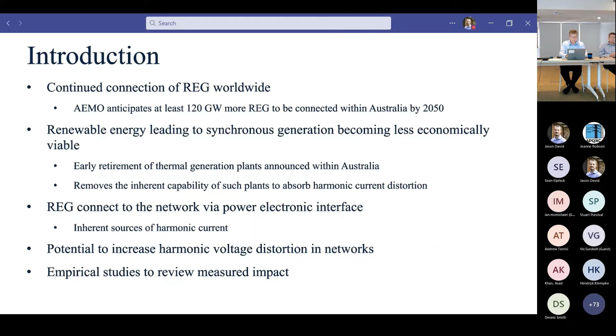And as already mentioned, quite often renewable energy generation will connect via a power electronic interface, which are inherent sources of harmonic current. So it's fair to assume that with all of these things happening, harmonic voltage distortion in general may increase as connections continue to be made and retirement of synchronous generation occurs.